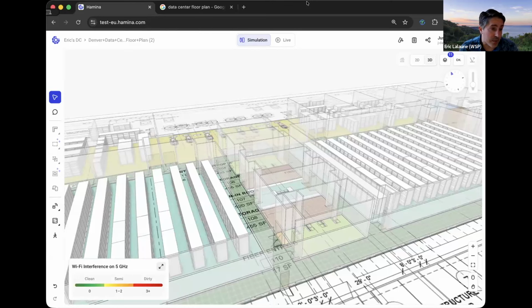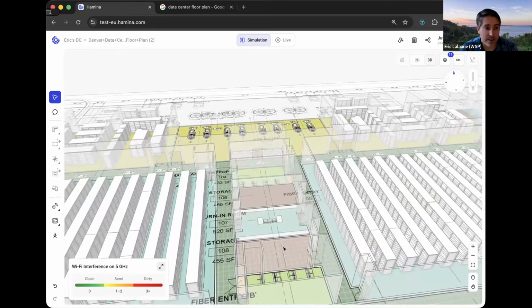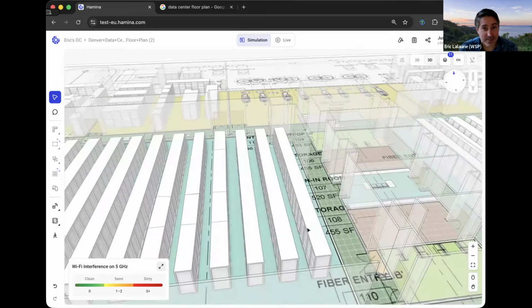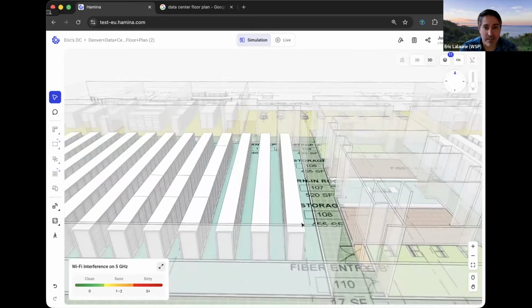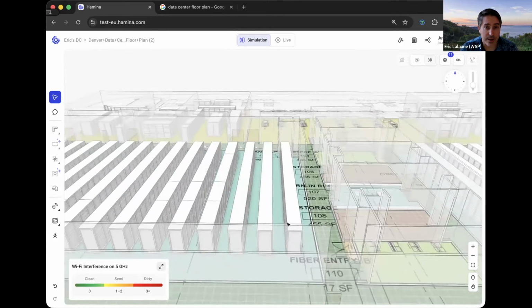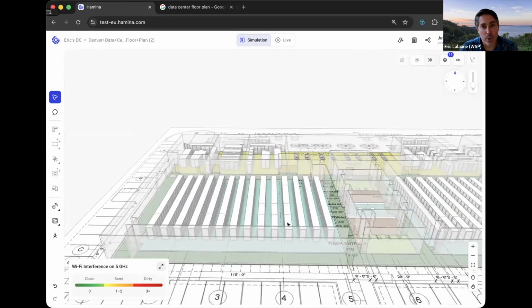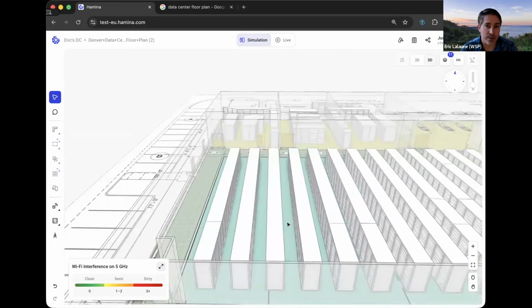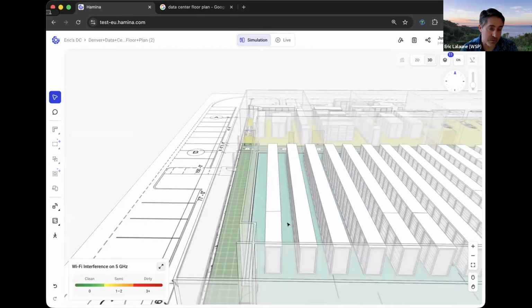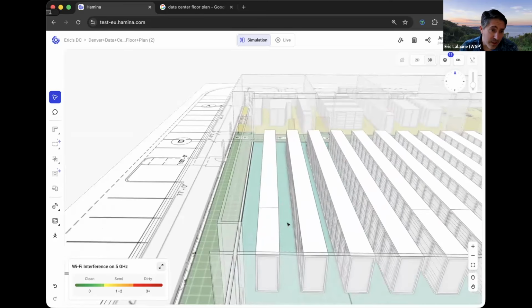If we look at your image here, starting from the wall, that's a cold aisle. Cold air blows through that aisle and is sucked into the servers or network equipment to cool them. That cold air warms as it goes through the equipment and is rejected at the back of the row. So you've got your first row as a cold aisle, then behind that another space between two server rows, that's a hot aisle. Essentially every rack row goes two by two: cold aisle, hot aisle, cold aisle, and so on. I don't know if it's spaced like that on this plan, but where your pointer is now would be a hot aisle.